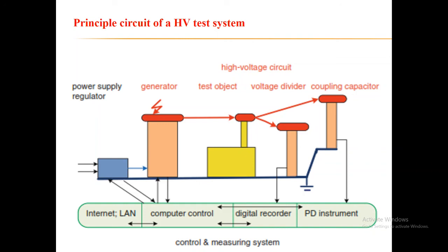Maximum amount of voltage is normally preferable to select, because if you are going with a very large magnitude of voltage, then you can imagine the cost of developing the high voltage laboratory. And apart from that, you need to take care of the severe conditions as well. Generally the voltage regulators use step up transformers, which can step up the voltage level from 415 volt or 11 kV to 220 kV for the testing purpose.